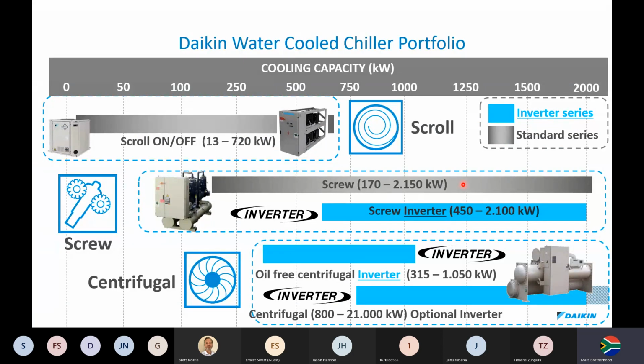So we are now going to go on to Daikin's water-cooled chillers. We've finished looking at the air-cooled ranges. We are now going to look at the water-cooled, with scroll capacities up to 700 kilowatts, as well as the chilled water screws. We do them in non-inverter up to 2.1 megawatts, inverter up to 2.1 megawatts. And then we do the centrifugal range. I'm not going to focus really on the centrifugal range, but we can go up to 21 megawatts. We have made chillers that big. It's a very, very specialized market, very special ordered chillers, but we can go up to 21 megawatts.